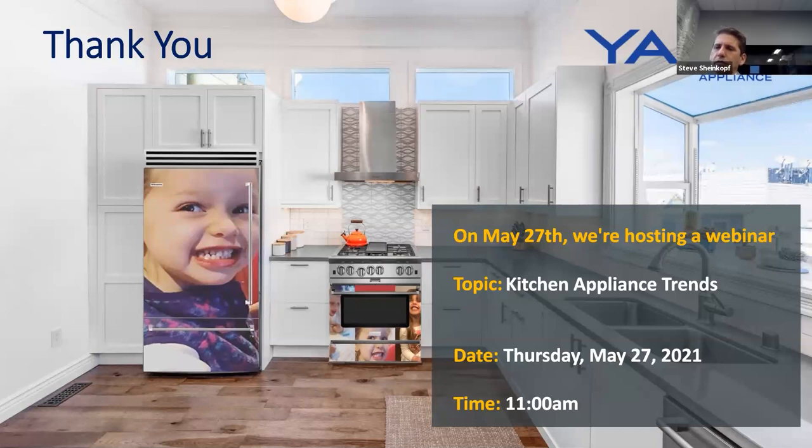I don't know if you pull permits or something, but typically, and Ricky, you'd have to, an inspector would not sign off on something without makeup air at this point. You've got to make up air somewhere. The other thing is if you're going to cook with your new pro range and your 1200 CFM, just remember you're getting 1200 cubic feet of air out of your house per minute. Open a window on the other side of your house if need be, but you're going to create a very unhealthy environment for your family if you don't.